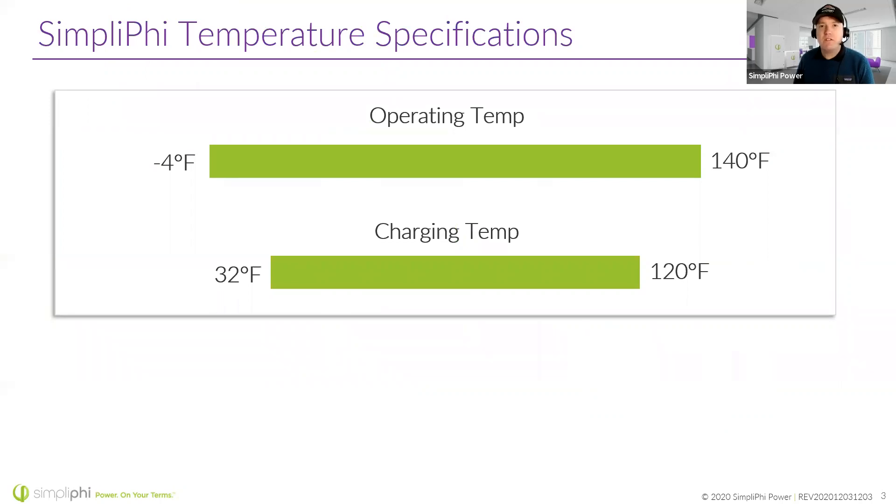Sorry about this — I realize as I was getting prepared this morning I should really have these in both Celsius and Fahrenheit. Any lithium ion battery shouldn't be charged below freezing. It is okay to leave it in a stable idle state and it's okay to discharge below freezing, but really what we want to see is that when you're charging a lithium ion battery — not just ours, but any manufacturer's — you're not charging it below freezing: 32°F (0°C) up to 120°F (approximately 49°C).